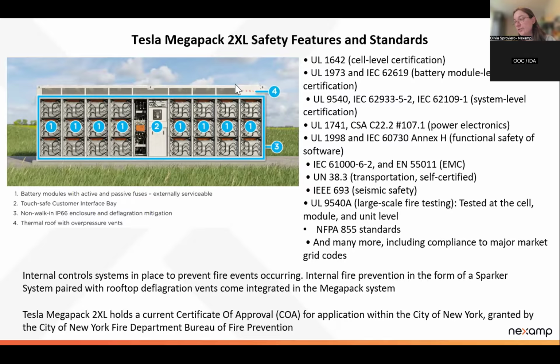So that's Tesla's active response. But as you probably know, you're not really supposed to put any water on these during a fire. They will burn themselves out. The way that they're separated, they should essentially burn out within 2 to 4 hours for the amount of fuel that is in each of their separated cell areas.